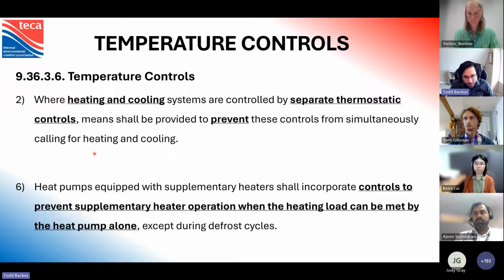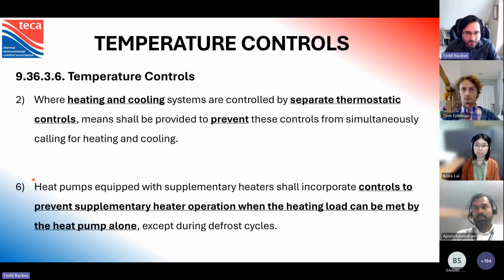So I would advise you to consider that when you're designing systems that could potentially be wrestling with each other, heating and cooling simultaneously. The other line here is heat pumps equipped with supplementary heaters shall incorporate controls to prevent supplementary heater operation when the heating load can be met by the heat pump alone, except during defrost cycles. So this I read as an argument against using the economic balance point, where you are setting up the system to switch to gas, say, if you have a furnace as a backup, in order to get cheaper energy. The code actually says you should really be using the heat pump 100% of its time. So the balance point should be set based on its efficiency rather than an economic set point, with the exception of the defrost cycle, which is logical.